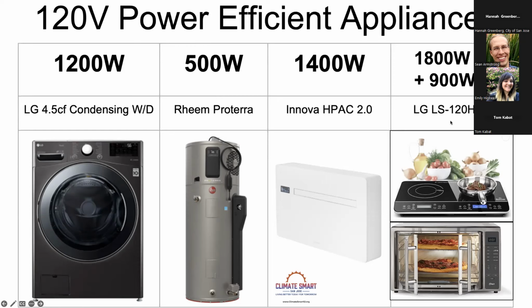I mean, if that's an issue, then maybe you need to put in the 60 amps, but most people would put in an 80 gallon heat pump water heater, which would be enough for like 10 showers in a row, or like 6 or 7 if people are really showering a long time.